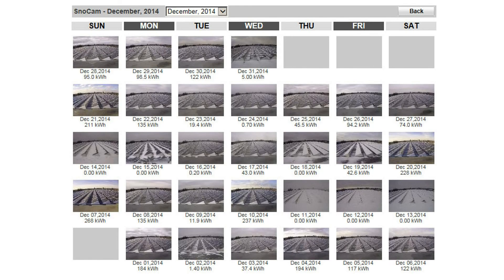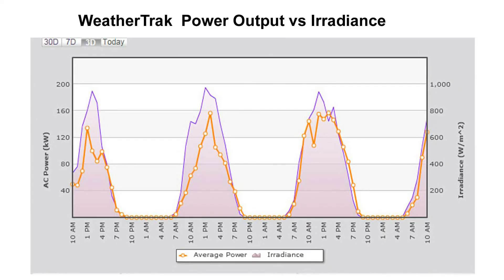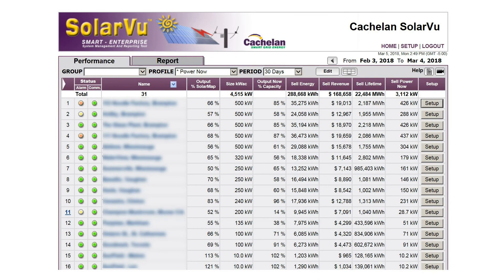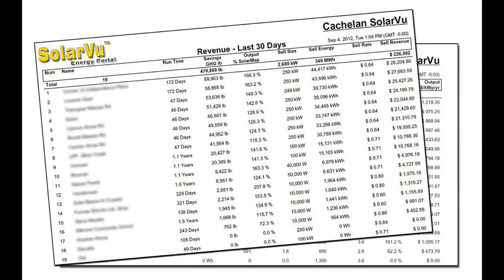SnoCam provides a daily photo record of site conditions, and WeatherTrak warns if the output of any inverter is below expected from the measured irradiance. Performance analysis shows variance to the original PVsyst design, and Smart Enterprise provides customized reports from over 50 available parameters.